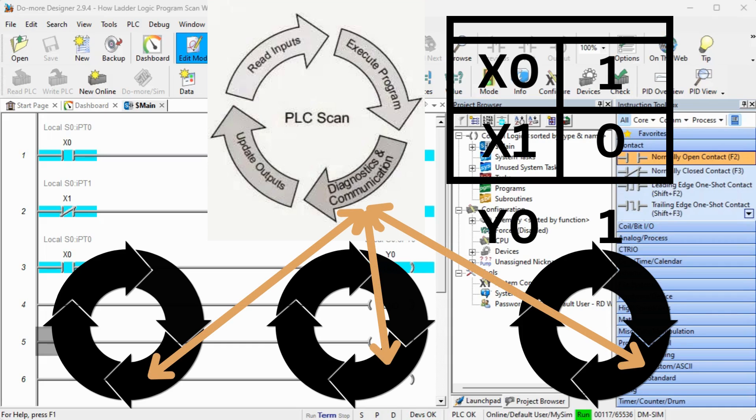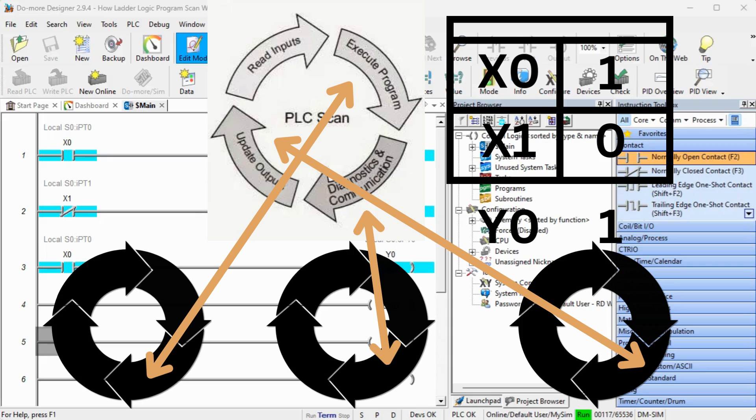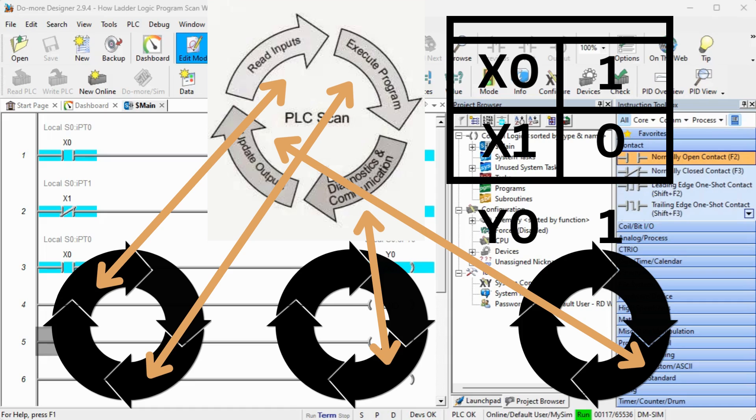The PLC scans, diagnostic, and communication part are where the PLC processors can share their data with the memory table. It is synchronous if the diagnostic and communication only happens once a PLC scan. This is asynchronous if this occurs at any time and the memory table gets updated any time or multiple times during the scan.